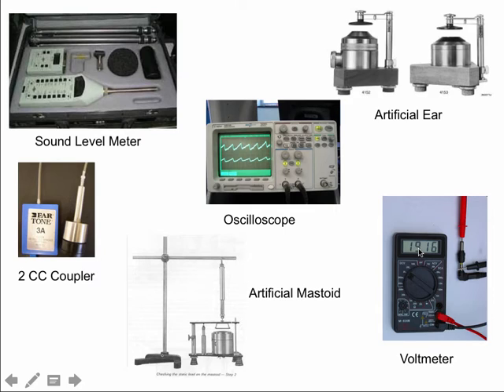So essentially, what makes audiometric calibration more specialized than calibration of any other physical equipment is the need for these devices that resemble the outer ear's mechanical impedance. In other words, when you're placing the headphone on a person's ear or an insert earphone, there is a certain amount of impedance offered by this external ear for the sound that's emitted by your insert earphone and your headphone. So you need to account for that when you're calibrating audiometric equipment, and hence the need for these different couplers. For instance, when you're using an artificial ear, it's designed to mimic the mechanical impedance that's offered by the headphone when it's placed on your pinna.